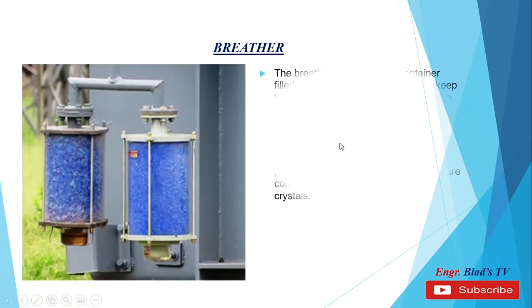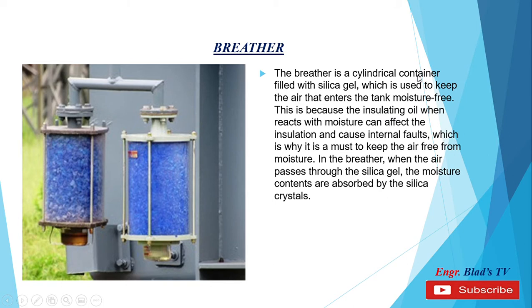The breather is a cylindrical container filled with silica gel, which is used to keep the air that enters the tank moisture-free. This is because insulating oil when it reacts with moisture can affect the insulation and cause internal faults, which is why it is a must to keep the air free from moisture. When the air passes through the silica gel, the moisture contents are absorbed by the silica crystals. Here is a sample of a silica gel breather — the blue color crystals are the silica gel.